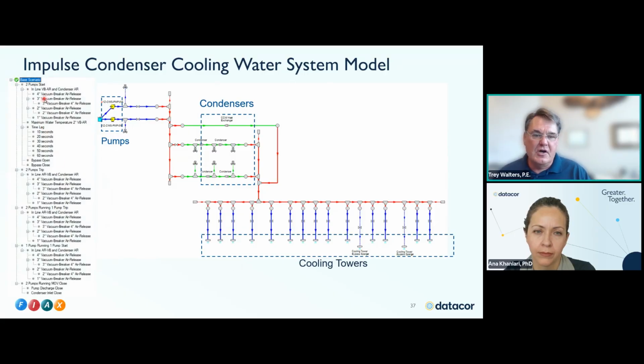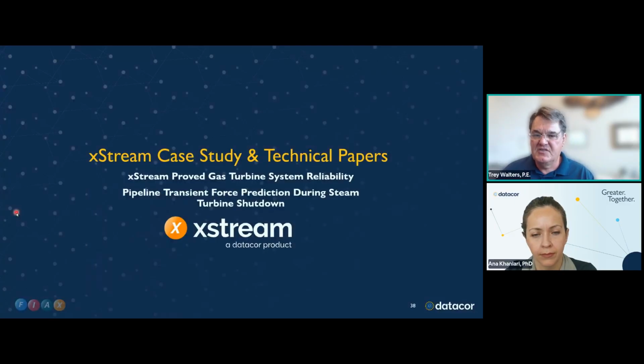These are all of the scenarios. This is a screenshot out of Impulse of all the different scenarios that they had set up and run to look at different types of cases in here. And you can see in here, they're looking at 2-pump start and 2-pump trip and one pump tripping, et cetera. All different cases you need to look at to make sure you've got a safe system.